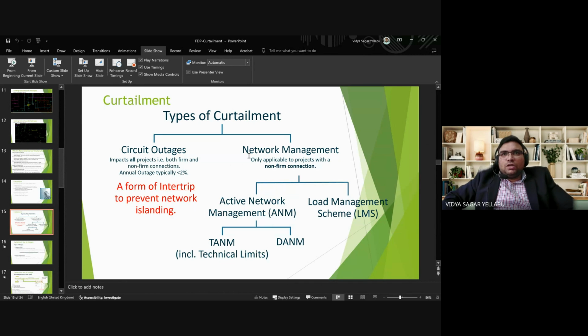And coming to network management, all the information of the network is communicated to a management system, which is called the active network management system, or ANM system. That ANM system uses data from the SCADA, supervisory control and data acquisition system, to monitor the status of the network. If it finds that some assets are getting overloaded because of some generation, then the ANM system sends signals to the associated generators that they have to reduce their generation so that these assets are not overloaded.